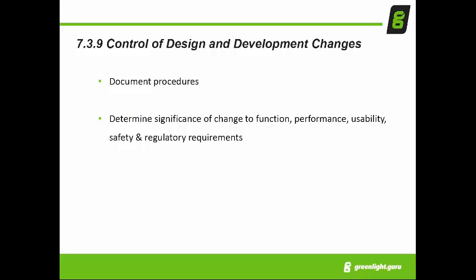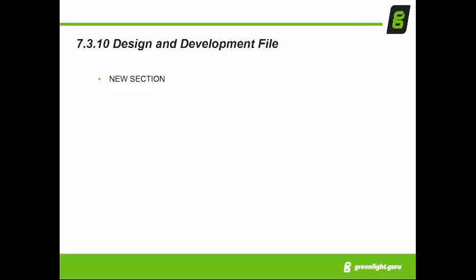Anytime you do that, you need to basically evaluate the impact of that change. How does it impact your form, fit, function? What does it do from a regulatory perspective? Do you have to go back and repeat some design and development activities? Does this trigger new design and development inputs? All of those things are factors as part of design and development changes.